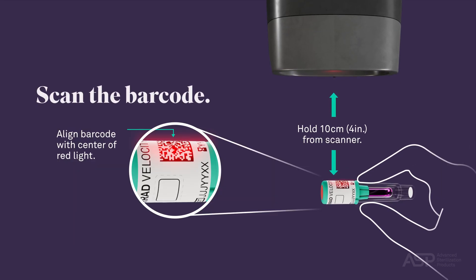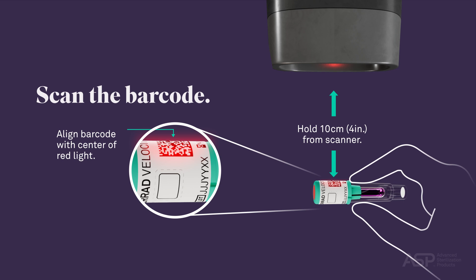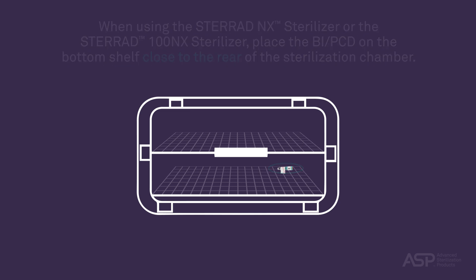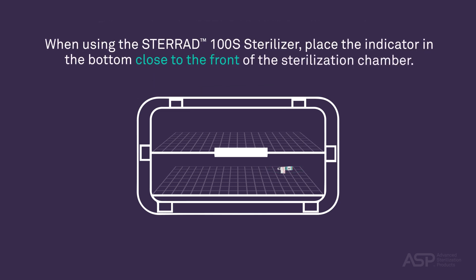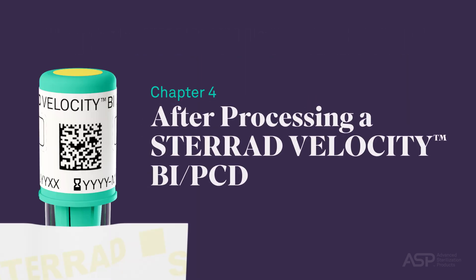If the STERRAD sterilizer is equipped with a scanner, scan the barcode on the cap label. When using the STERRAD NX Sterilizer or the STERRAD 100 NX Sterilizer, place the BI PCD on the bottom shelf close to the rear of the sterilization chamber. When using the STERRAD 100S Sterilizer, place the indicator on the bottom close to the front of the sterilization chamber.